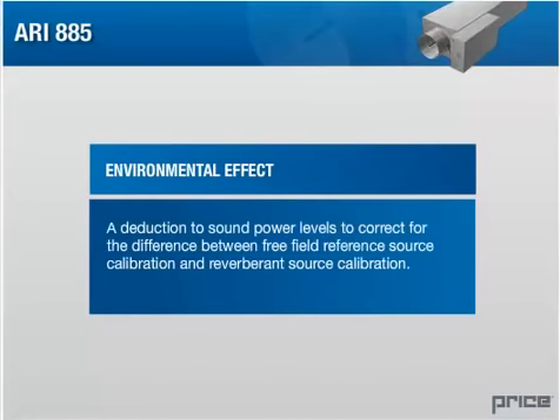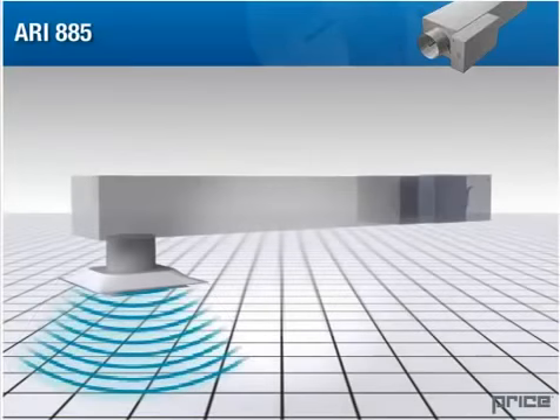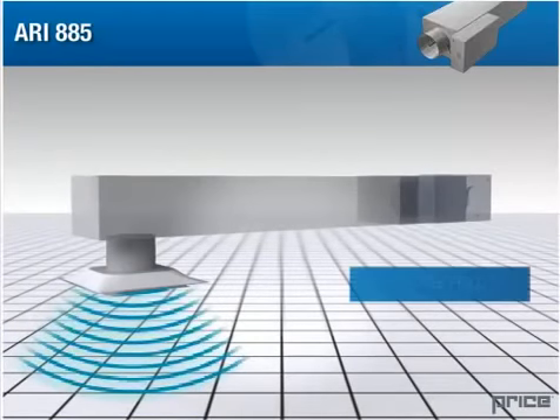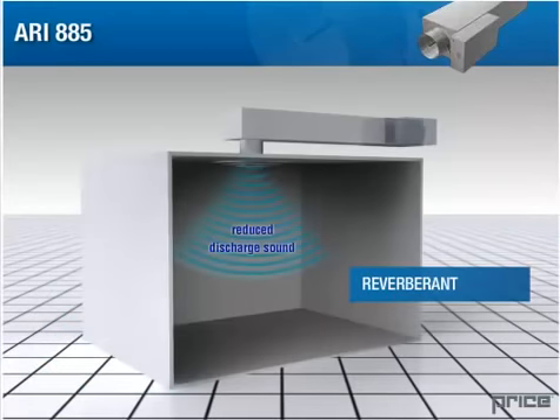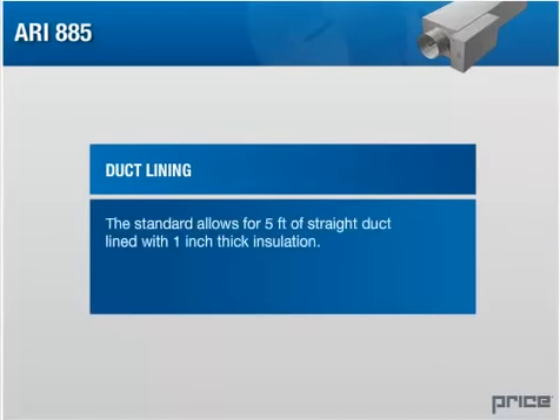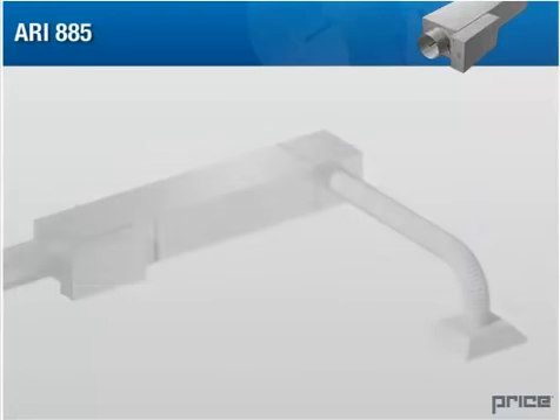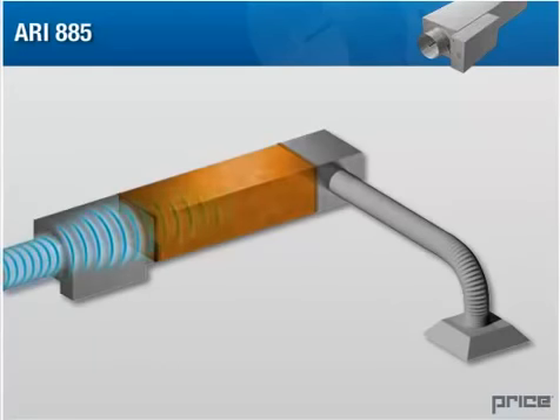Environmental effect. A deduction to sound power levels to correct for the difference between free field reference source calibration and reverberant source calibration. Performance data obtained in accordance with ARI 880 are equivalent to free field power levels, but all real occupied spaces behave acoustically more like reverberant rooms. An average-sized room will tend to dampen lower frequencies found in the discharge sound due to cancellation effects. Duct lining. The standard allows for 5 feet of straight duct lined with 1-inch thick insulation. This lined duct will absorb some of the discharge sound as it travels down the duct, so deductions are made to account for this.